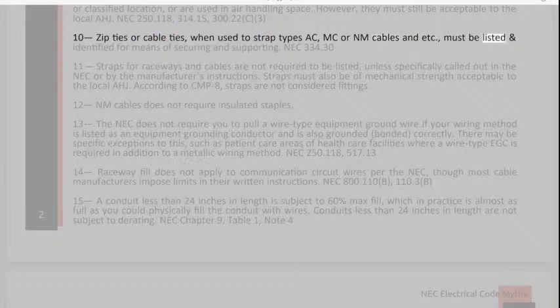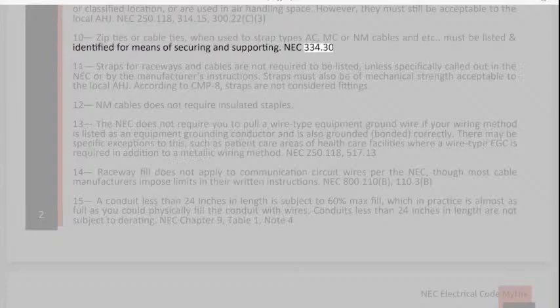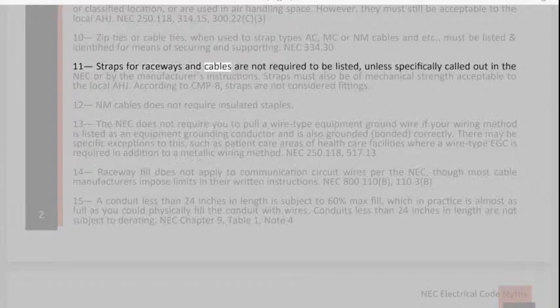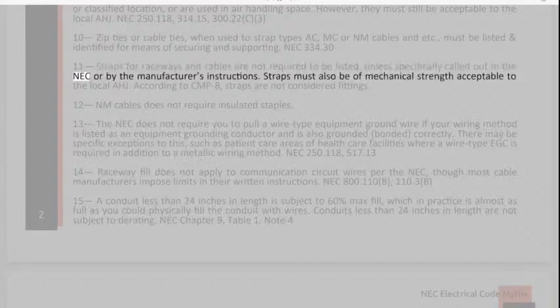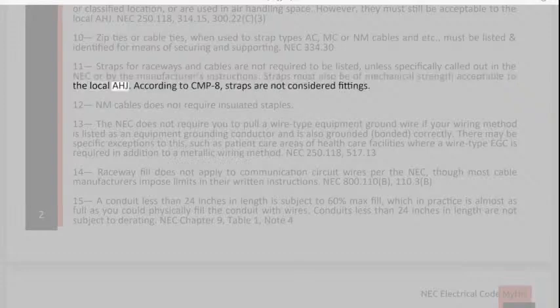10. Zip ties or cable ties, when used to strap types AC, MC or NM cables, etc., must be listed and identified for means of securing and supporting. NEC 334.30. 11. Straps for raceways and cables are not required to be listed, unless specifically called out in the NEC or by the manufacturer's instructions. Straps must also be of mechanical strength acceptable to the local AHJ.